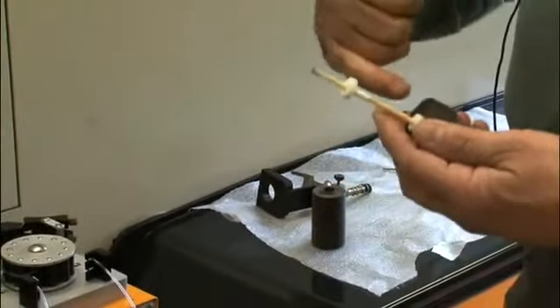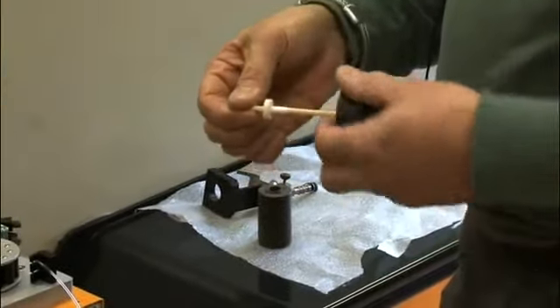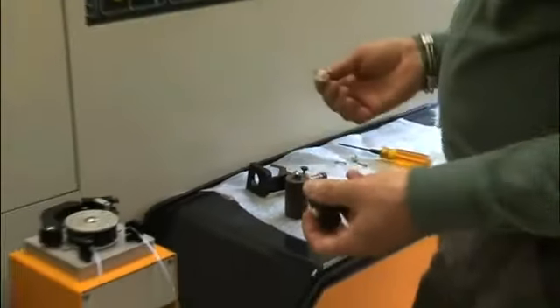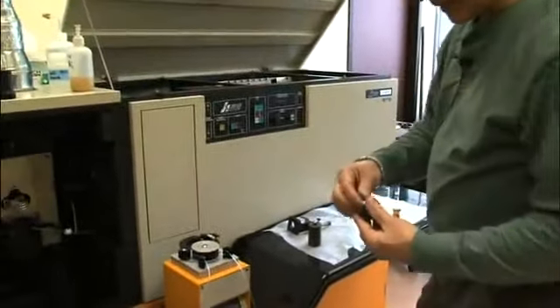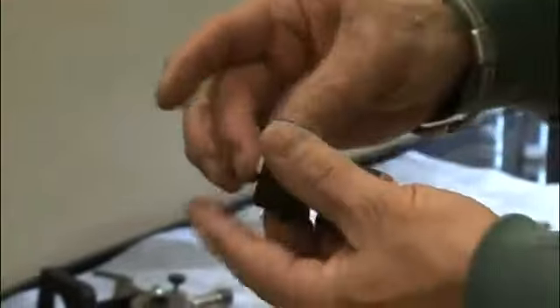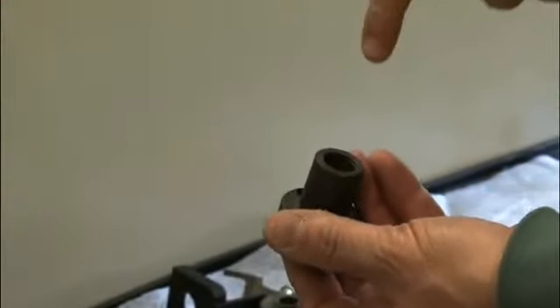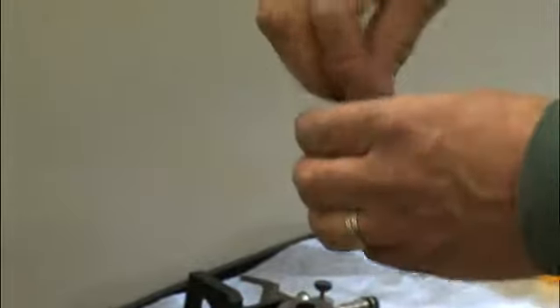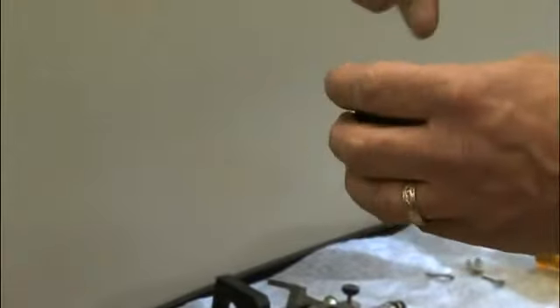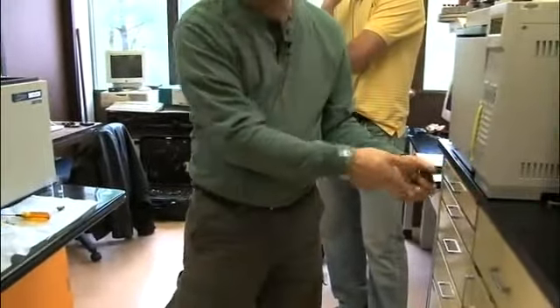Otherwise, if you get air coming in through here, your results will be all to hell. This injector, if you need to replace this Teflon insert, what I do is I take a hex key, put it through this end and smack it because it's in there pretty tight. To put a new one back in, you just push it in, and I normally push against something until it stops. You'll feel it stop.